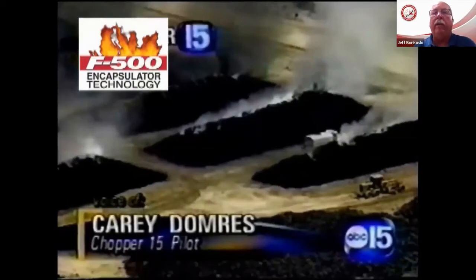Okay, I'm going to stop it there. I think it's kind of made the point. It talked about a few things. One, just how rapidly that fire was able to spread from one pile of tires to the next until all of them were involved. Again, encapsulator agent early on could have kept that fire to just that one pile. They talked about the impact on the community, the evacuations that this fire caused, and the impact that it had for days and days and days. But then once they received the F500 encapsulator agent, how quickly they were able to get this fire under control. Foams, waters, and other things didn't work.